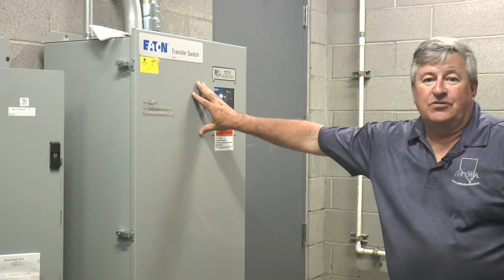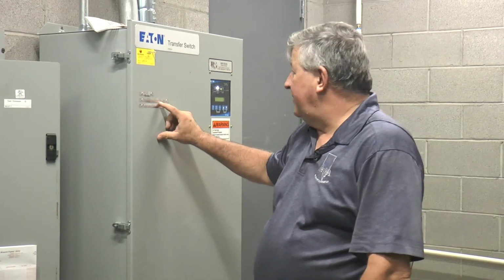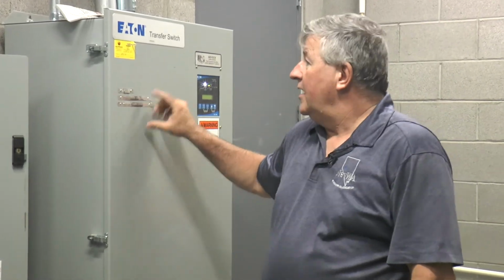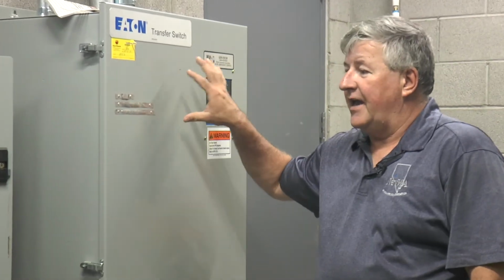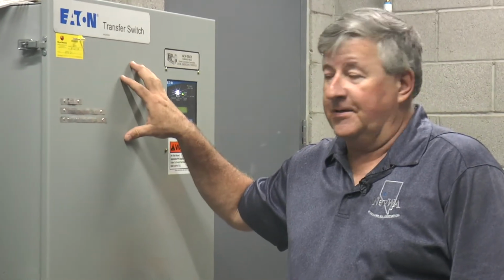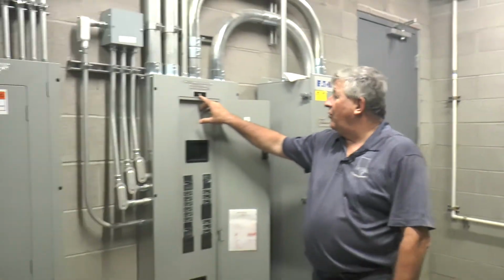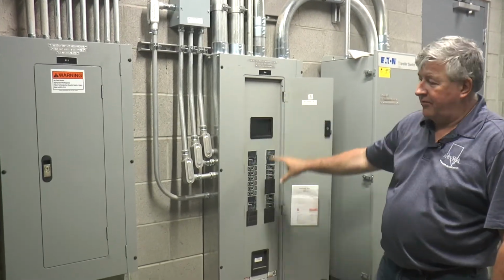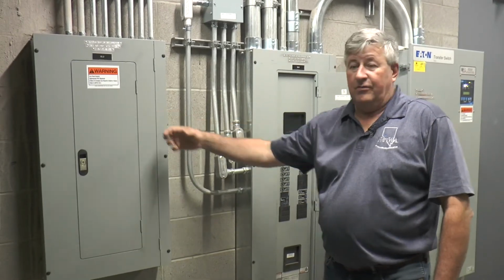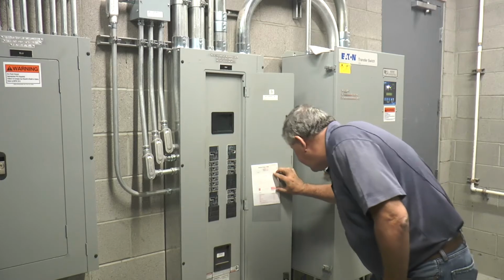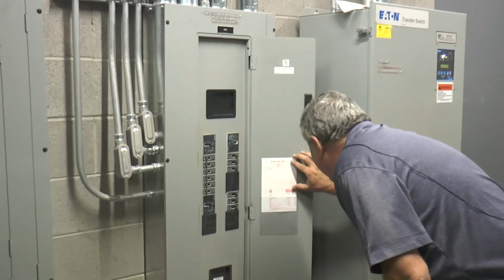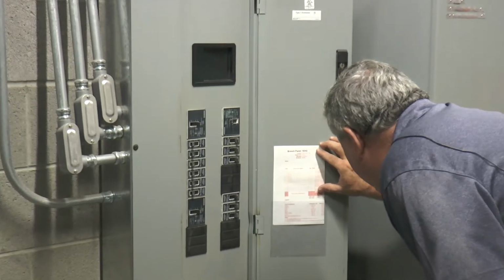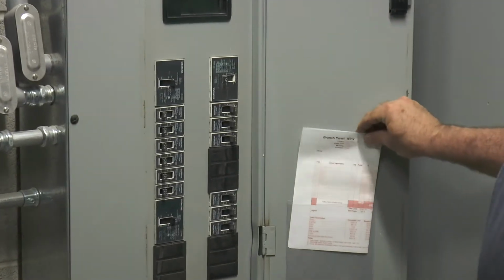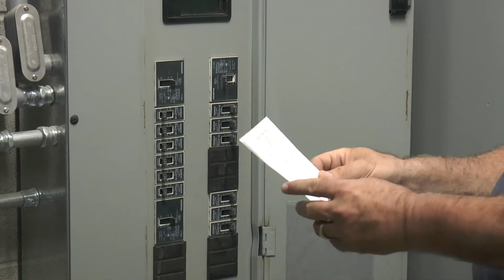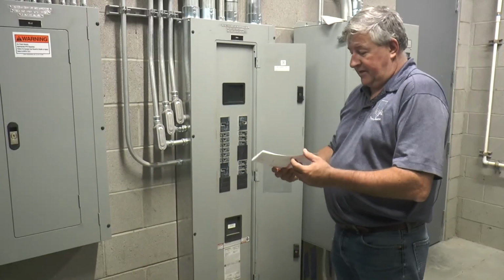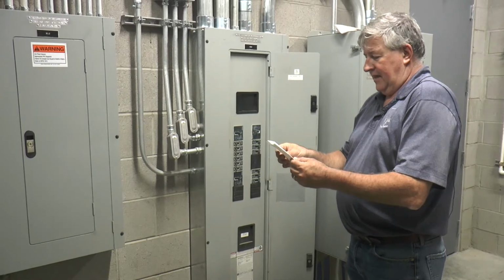This is transfer switch number 2 connected to the generator set, being fed from switchboard number 1, normal power. This transfer switch backs up your elevators and all your standby loads in the building. It is feeding 1 EH2, which is your high voltage panel, through a transformer into EL2, which is low voltage. Your panel schedule here, I can read the small font. Jockey pumps, most of it's probably domestic water on here, that type of stuff. Equipment, water pressure, jockey pump. Supply fans? Yep, for the stairwells. And then the transformer. Okay.